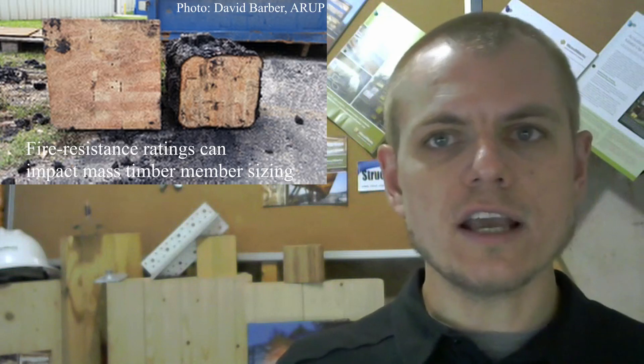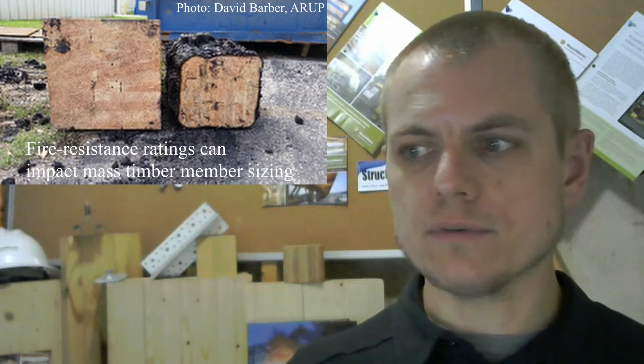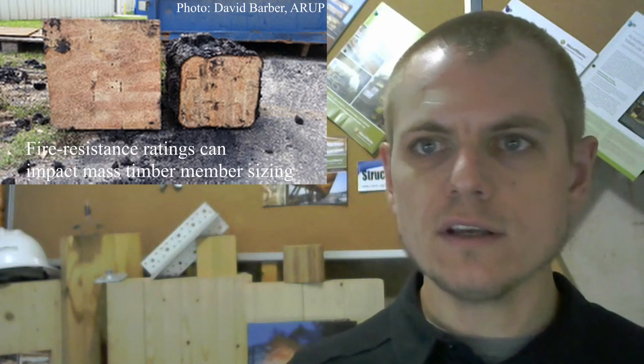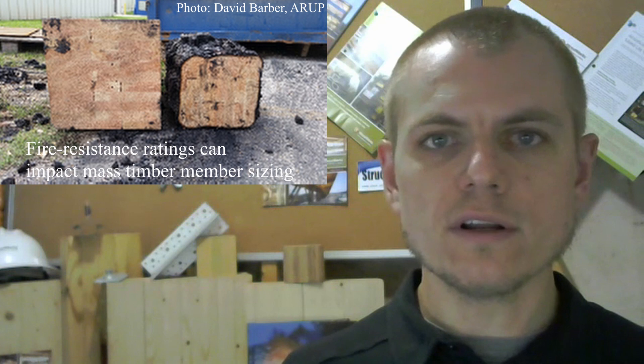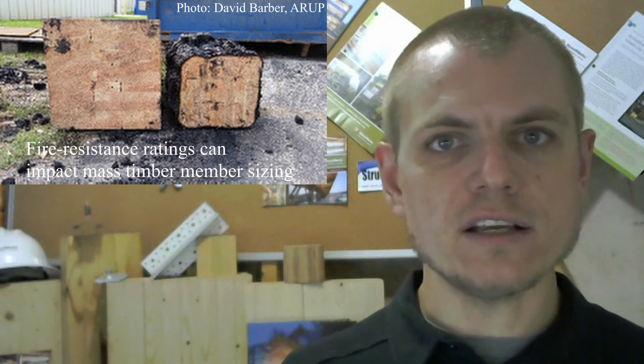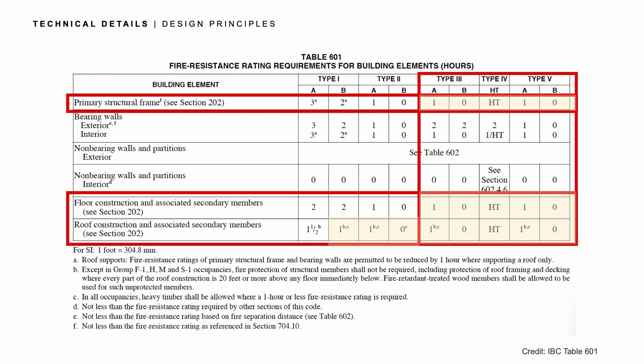For example, if we're looking at construction types 3B, 4, and 5A as options, there are some very significant differences in what we need for fire ratings within those. 3B structure really has zero hourly fire ratings for most interior structural elements.